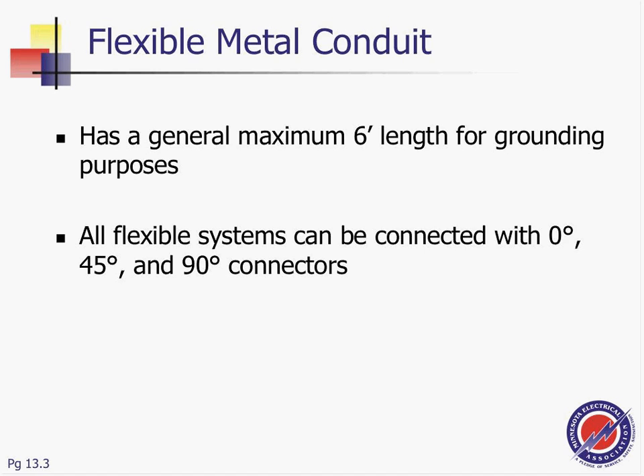Okay, flexible metallic conduit has a general maximum length of 6 feet. Now, guys, to use flexible metallic conduit, equipment grounding conductor. Very interesting. If I have a fixture, so you have your lighting fixtures right in here, you have your 4 lighting fixtures, as you guys probably have seen. So you bring your J box right in here. Conduit coming in, conduit coming out, and from this box you flex to this one, and you flex to that one, and you flex to this one, and you flex to the other one. So here's my J box right in here, and each one of these is a light, and light, and light, and light. That's the application, guys, for a flex.